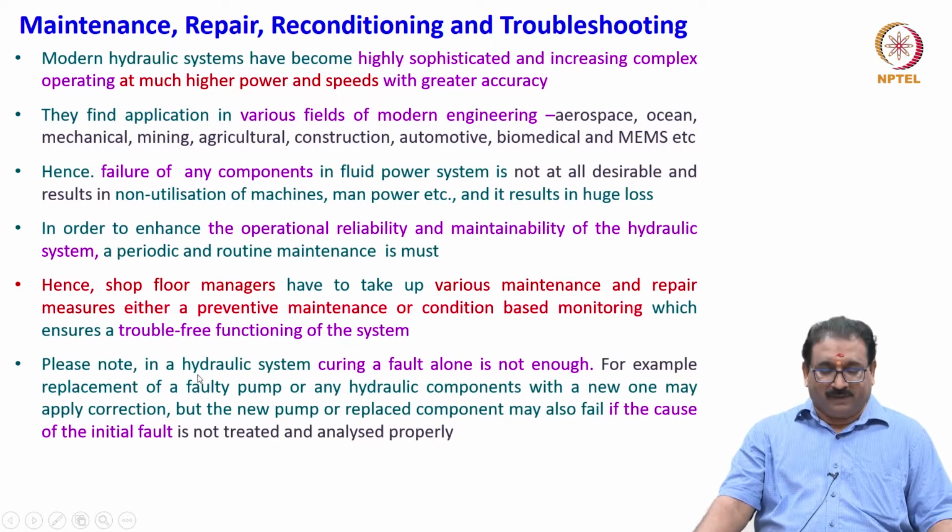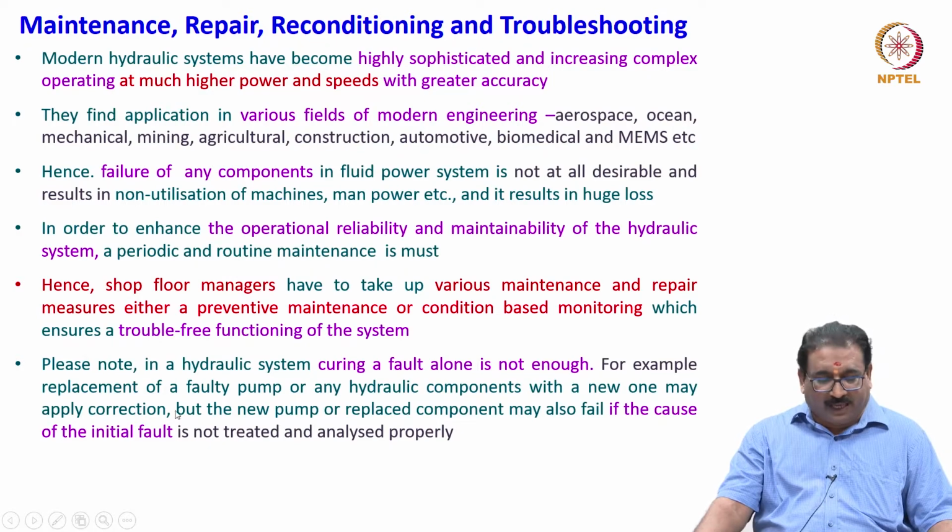Please note, in a hydraulic system, curing a fault alone is not enough. For example, replacement of a faulty pump or any other component with a new one may apply a correction, but the new pump or replaced component may also fail if the cause of the initial fault is not treated and analyzed properly.